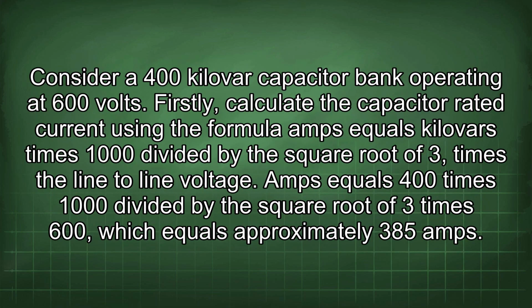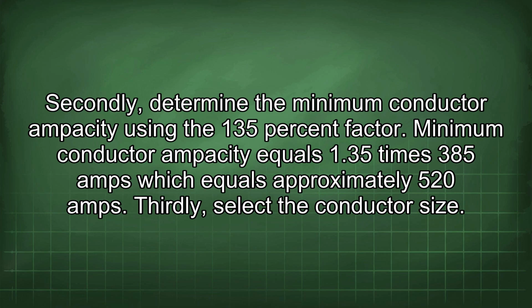Consider a 400 kVAR capacitor bank operating at 600 volts. Firstly, calculate the capacitor rated current using the formula amps equals kilovars times 1000 divided by the square root of 3 times the line-to-line voltage. Amps equals 400 times 1000 divided by the square root of 3 times 600, which equals approximately 385 amps. Secondly, determine the minimum conductor ampacity using the 135% factor. Minimum conductor ampacity equals 1.35 times 385 amps, which equals approximately 520 amps. Thirdly, select the conductor size.